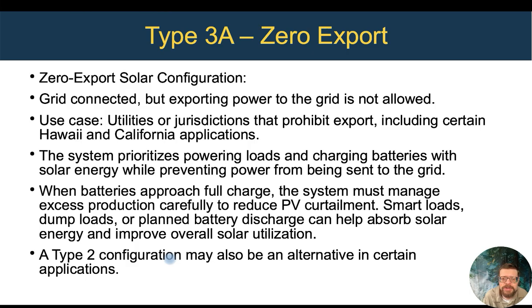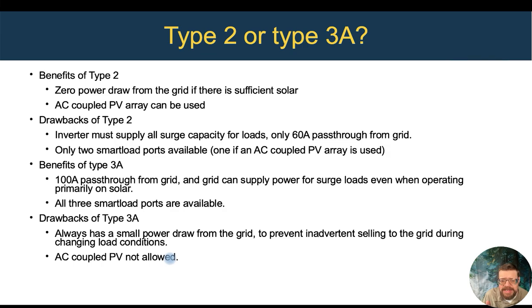So we're operating very much like we just described for a type 2 system. We're operating from our own batteries, trying to avoid drawing from the grid as much as possible. And if the batteries get full, we use the smart loads in the inverter to turn on opportunity loads, like when we turn on the EV charging or turn on an electric water heater just to store hot water, rather than just curtailing that PV production that we're not allowed to sell once our batteries are full. Often when you are dealing with a grid where you're not allowed to export, you might want to also look at a Type 2 configuration instead of a Type 3A. And we'll look at some of the benefits and drawbacks, and what the difference is there.